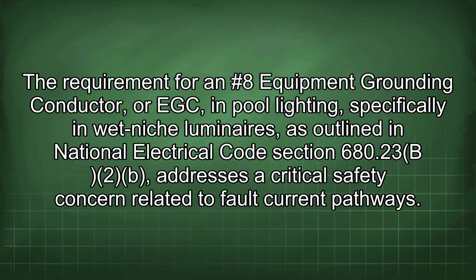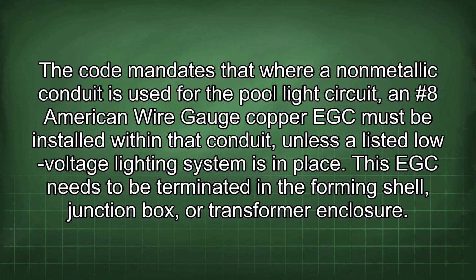The requirement for an #8 equipment grounding conductor, or EGC, in pool lighting, specifically in wet niche luminaires, as outlined in National Electrical Code Section 680.23(B)(2), addresses a critical safety concern related to fault current pathways. The code mandates that where non-metallic conduit is used for the pool light circuit, an #8 American wire gauge copper EGC must be installed within that conduit, unless a listed low-voltage lighting system is in place. This EGC needs to be terminated in the forming shell, junction box, or transformer enclosure.